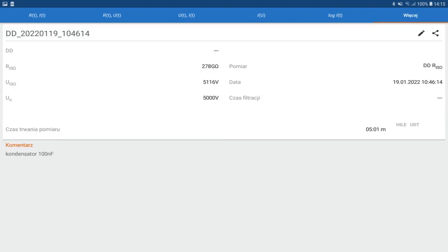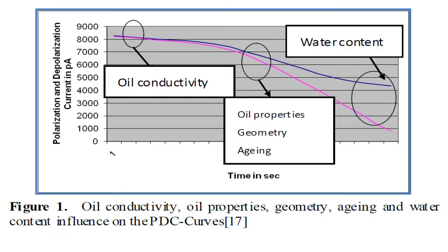The sixth, the last tab is measurement parameters. So how to analyze it? The characteristics of the polarization and depolarization current should be more or less parallel. They should not cross or differ from each other. The depolarization current plot should be smooth.